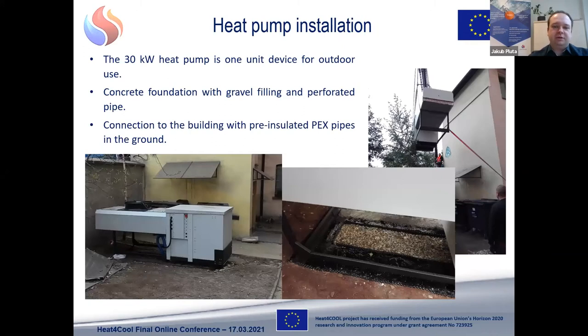The heat pump installed in the building is an outside unit with 30 kilowatt power. It stands on a concrete foundation previously prepared, which is inside filled with gravel. Under this is a perforated pipe, which allows us to direct the condensate directly to the rain sewage system. As the heat pump is around 11 meters from the building, the pipes connecting the basement of the building with the heat pump are twin pre-insulated pipes, which run in the ground.